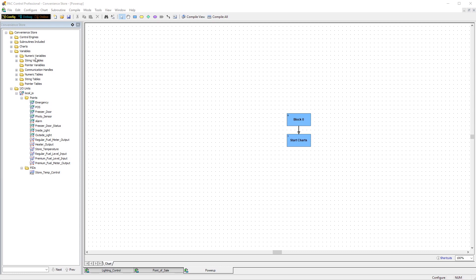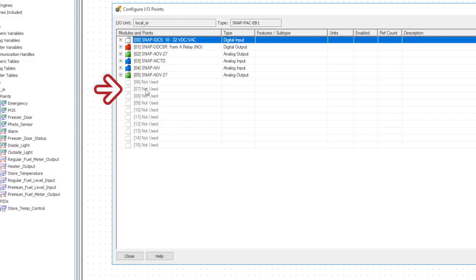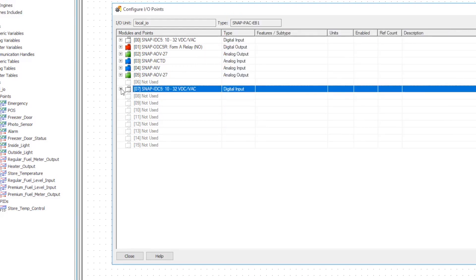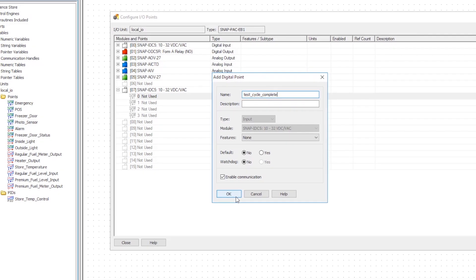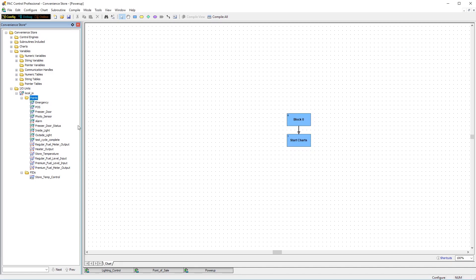Here we are in PAC Control. We've already got our I/O rack configured. Now let's double click on the empty slot in position 7 to add our digital input module, a SNAP IDC5. Double click on the first point of the module and open the point configuration dialog. Now we can give the proximity sensor a tag name like 'test cycle complete'. This is where you give the sensor a meaningful name for all of your software applications or cloud services, so make sure you choose your name accordingly.